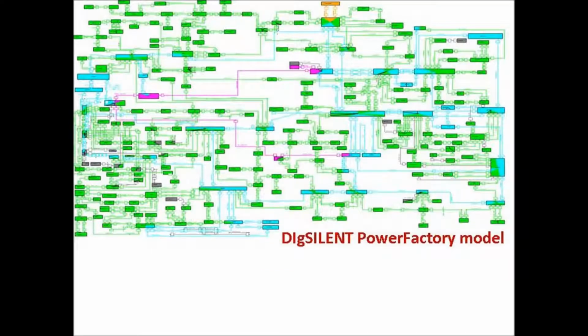Then we start doing the modelling. We have a model of the entire system. We use DIgSILENT PowerFactory. It models every single node, every single circuit breaker, every single generator. Not all the loads are modelled in the greatest of detail; we don't go down to 230 volts. We would only model down as far as 38 kV and DSO connected nodes. So you've got your PowerFactory model.